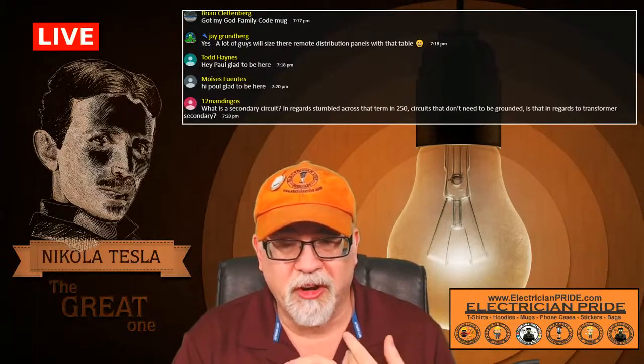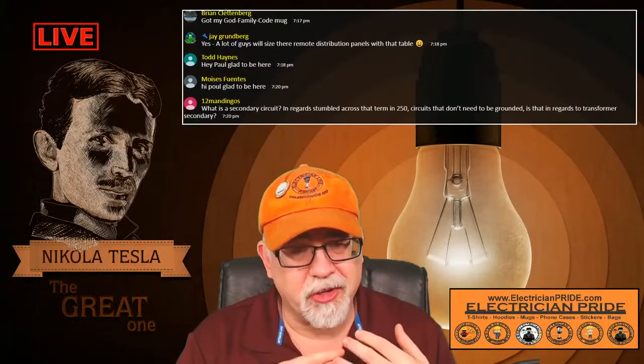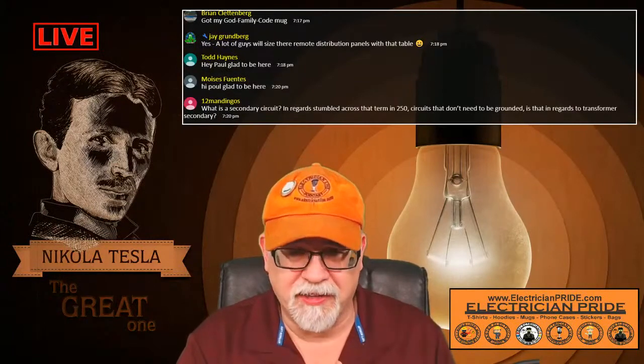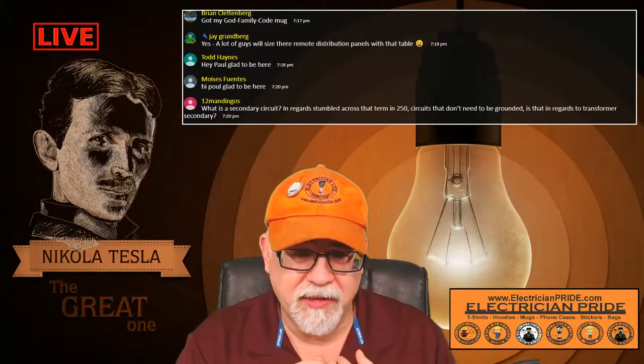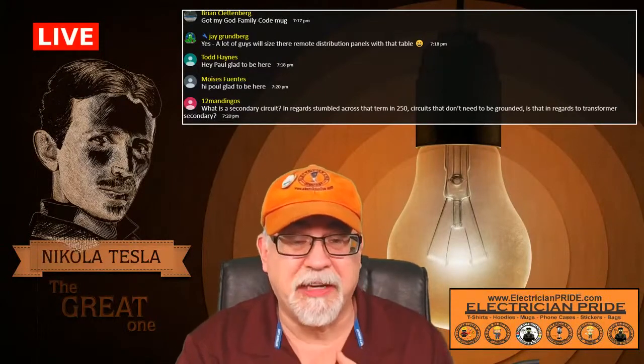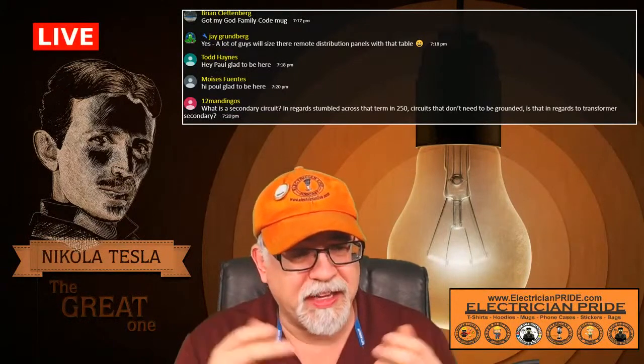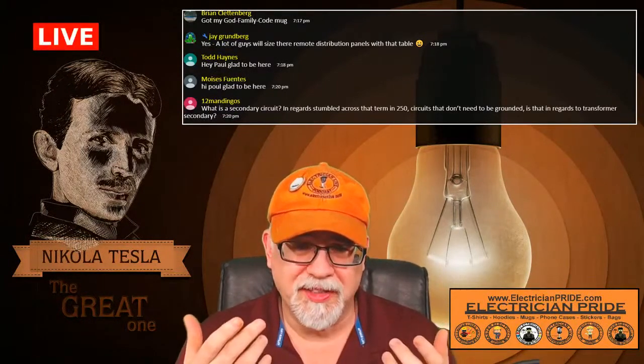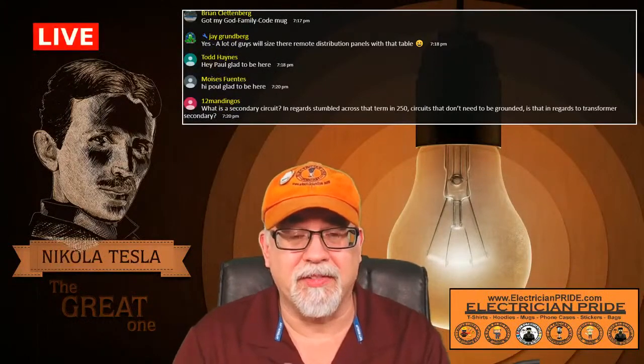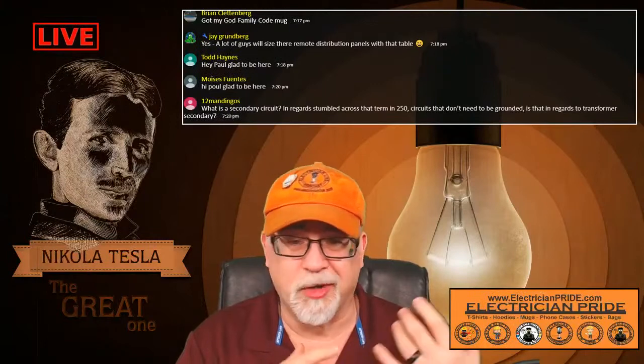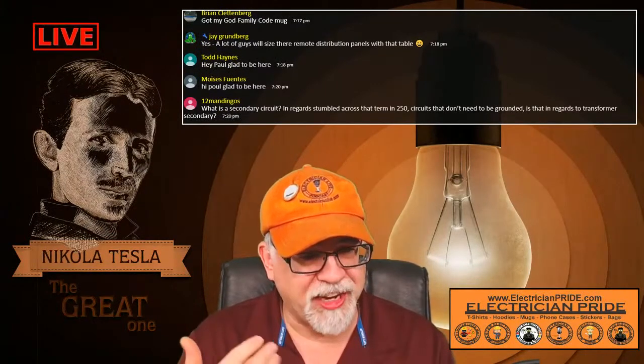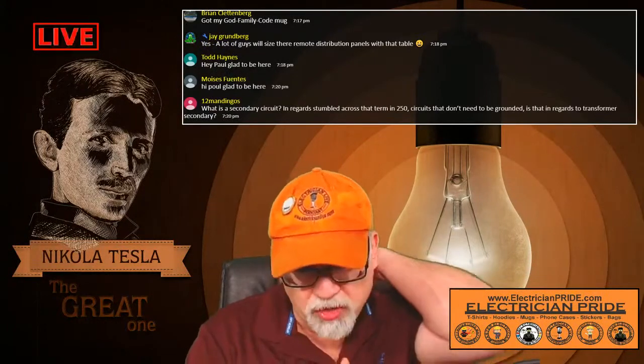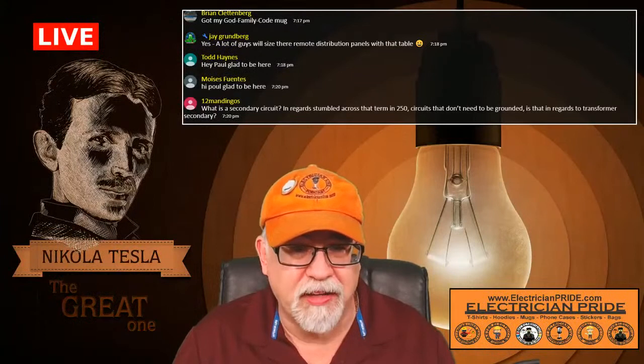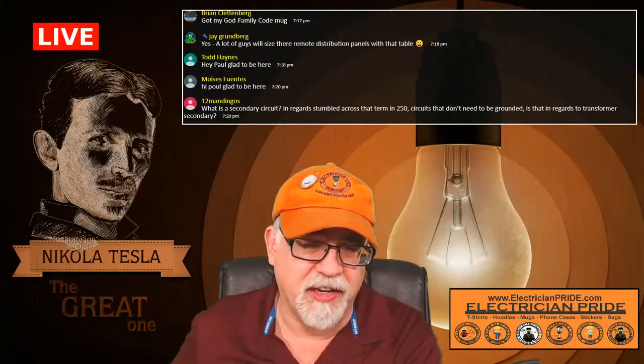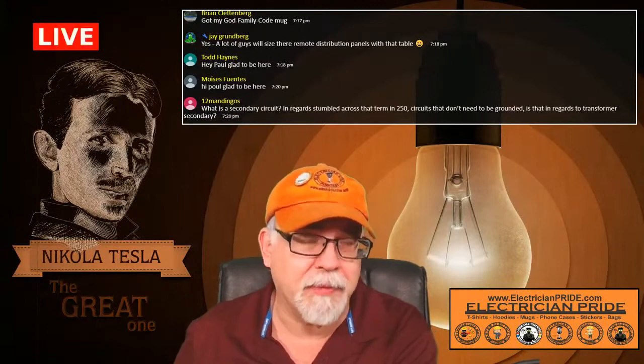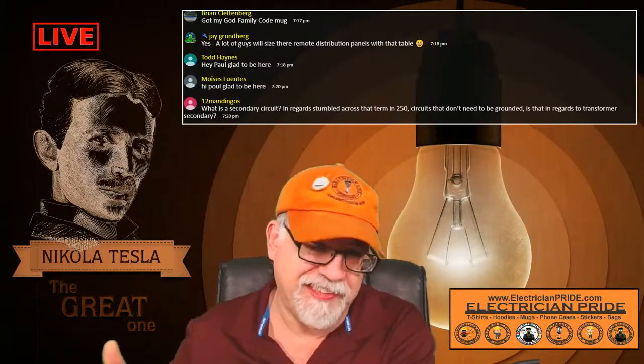When it comes to circuits, you have grounded circuits, ungrounded circuits, circuits required to be grounded, some permitted to be grounded, and some that specifically say they're not to be grounded at all. A good example, without getting too deep, is a doorbell transformer. You take a primary side to it with an equipment ground, but on the secondary side, those secondary circuit conductors - which may be a 120 to 24 volt transformer - those secondary circuit conductors would not be required to be grounded, if you will.